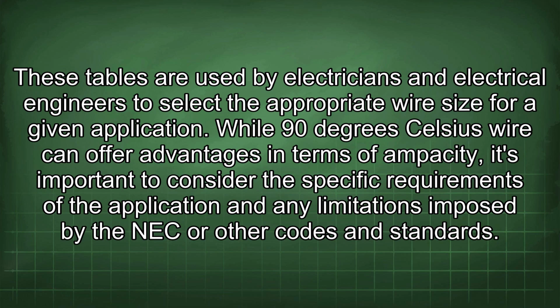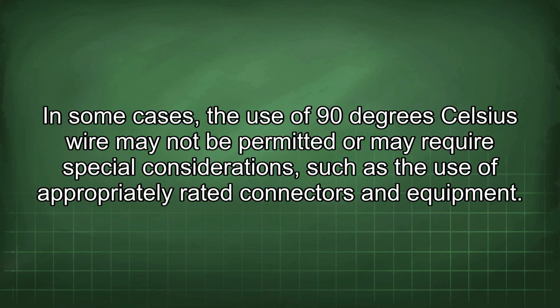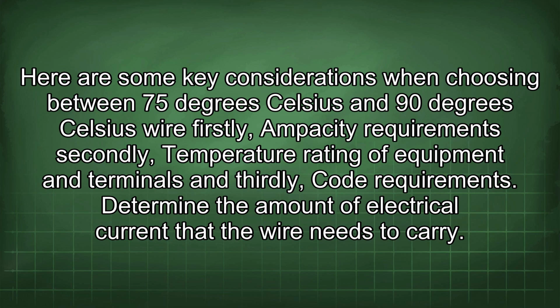While 90 degrees Celsius wire can offer advantages in terms of ampacity, it's important to consider the specific requirements of the application and any limitations imposed by the NEC or other codes and standards. In some cases, the use of 90 degrees Celsius wire may not be permitted or may require special considerations, such as the use of appropriately rated connectors and equipment. Here are some key considerations when choosing between 75 degrees Celsius and 90 degrees Celsius wire. Firstly, ampacity requirements. Secondly, temperature rating of equipment and terminals.